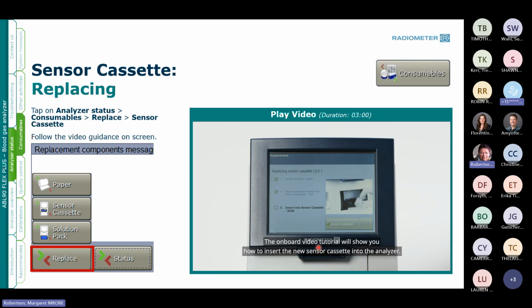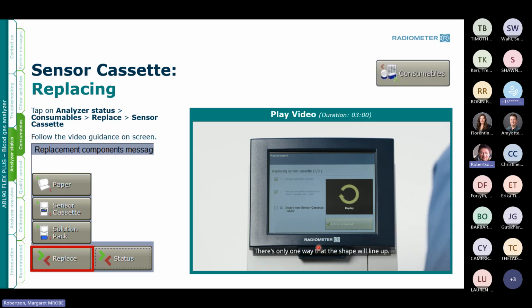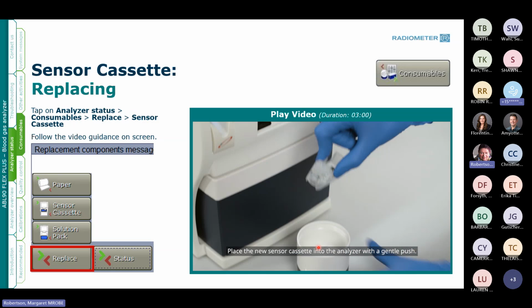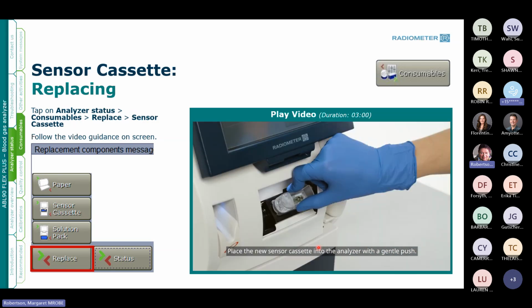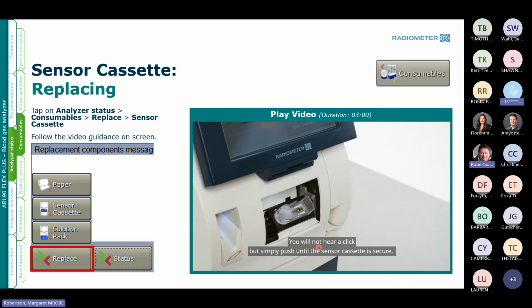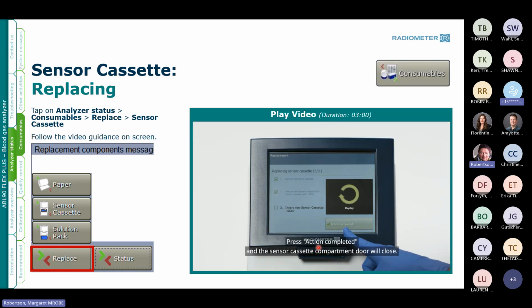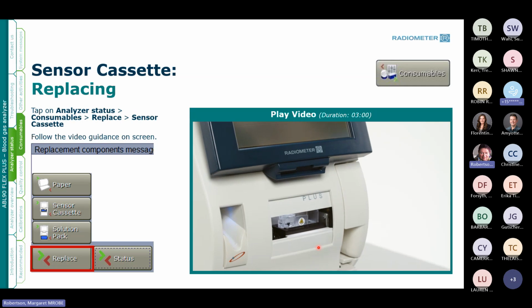The onboard video tutorial will show you how to insert the new sensor cassette into the analyzer. Because of the way that the sensor cassette is shaped, it is not possible to insert it backwards. There's only one way the shape will line up. Place the new sensor cassette into the analyzer with a gentle push. You will not hear a click, but simply push until the sensor cassette is secure. Press Action Completed, and the sensor cassette compartment door will close.